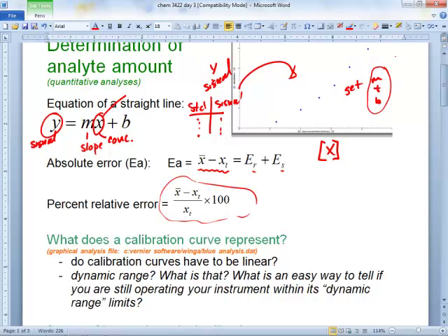Okay, the other thing you got to be careful on is, and I'll nail you for this, right? There's my signal range. I'm looking at these two endpoints. That one and this one. So right there and right here. This is my concentration range. This is my signal range.